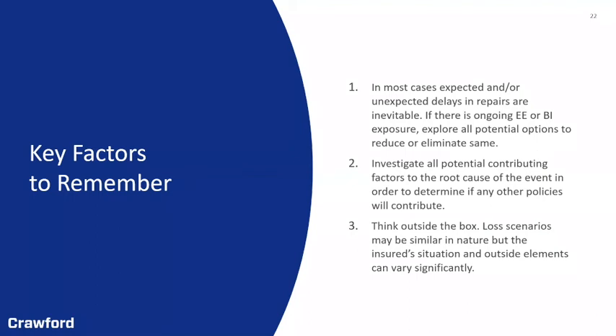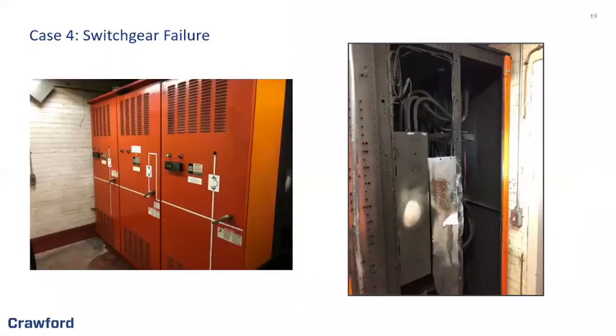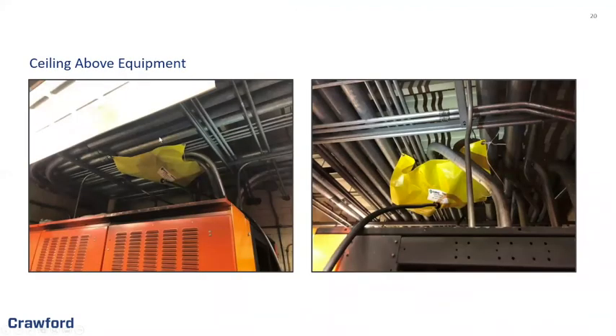Second key factor: investigate all potential contributing factors to the root cause of the event, to determine if other policies will contribute. The fourth case speaks to this, where we had failure of the automatic transfer switch. If you recall, we discovered that water had leaked through the ceiling into the unit, resulting in the short and failure of same.